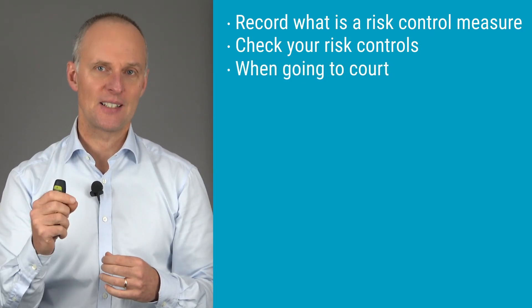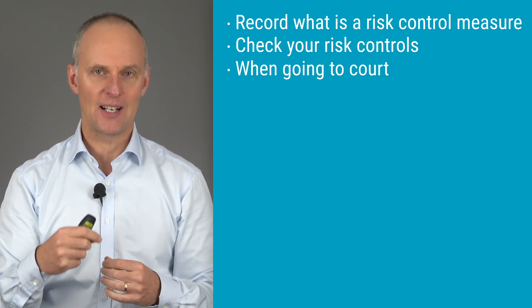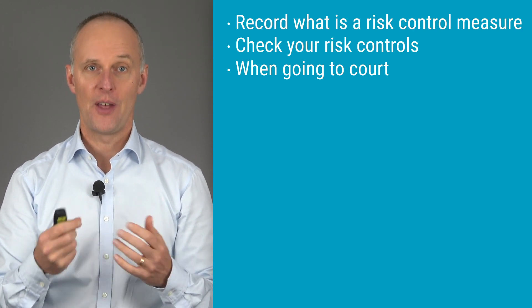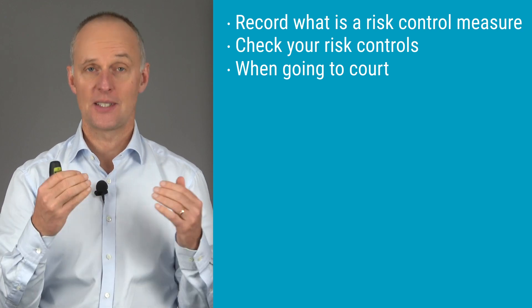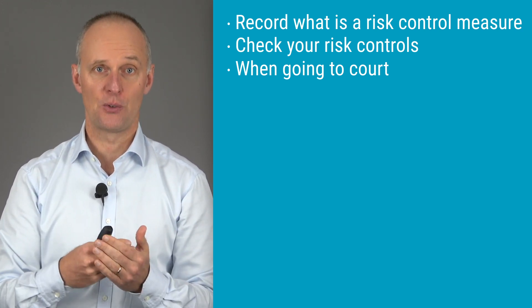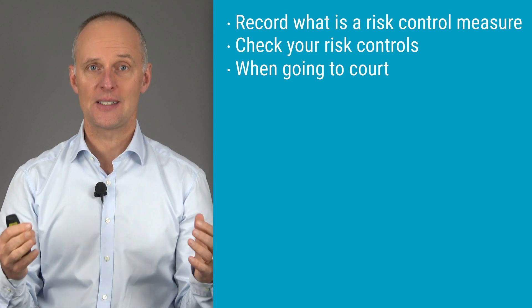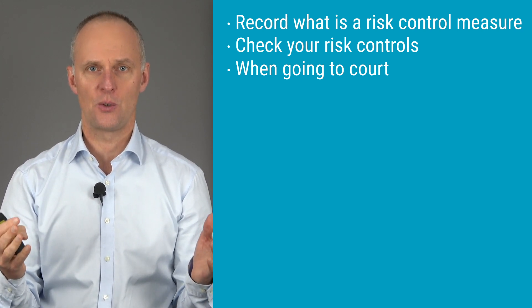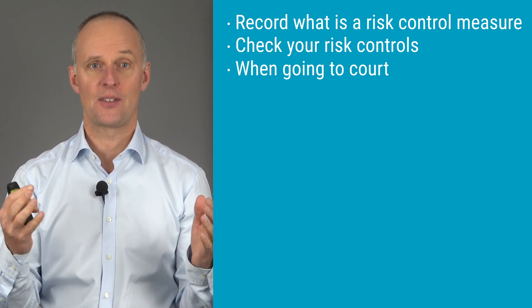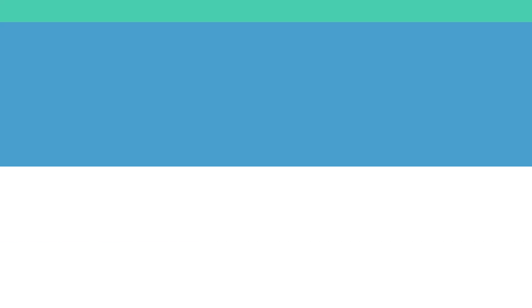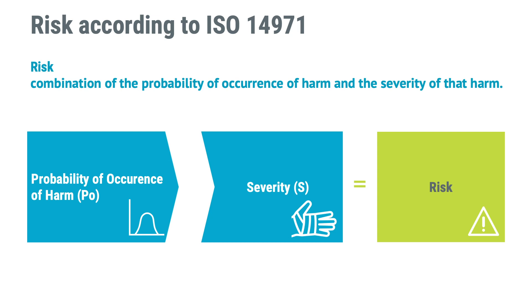Last but not least, if an accident occurs and someone is injured and it leads to a trial, then it is much better to be able to show that you decided to implement insulation of cables, an insulating cover on the device, and an earth connection — as opposed to just taking these risk controls for granted. Before we start looking at estimating risks, let's take a look at what risk is according to ISO 14971. In the ISO 14971 standard, risk is defined as the combination of probability of occurrence of harm and the severity of that harm.